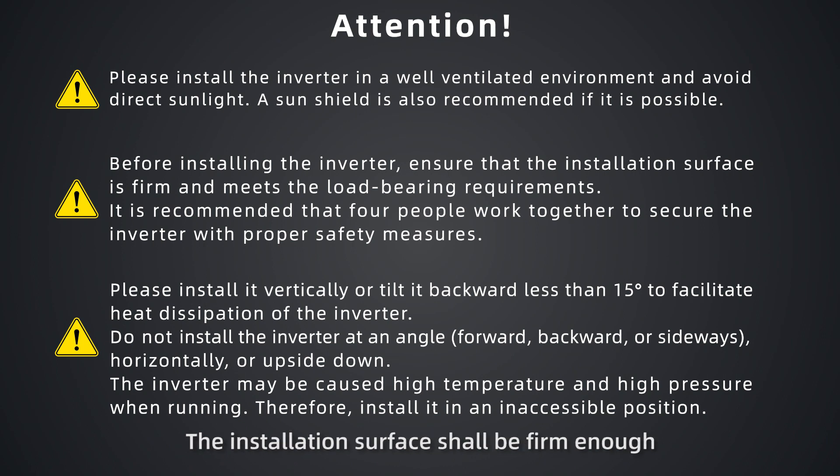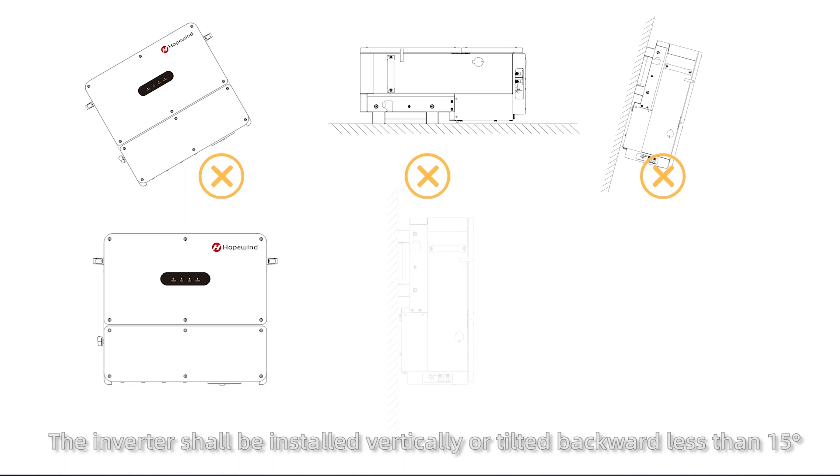The installation surface shall be firm enough and meet the load-bearing requirements. The inverter shall be installed vertically or tilted backward less than 15 degrees.